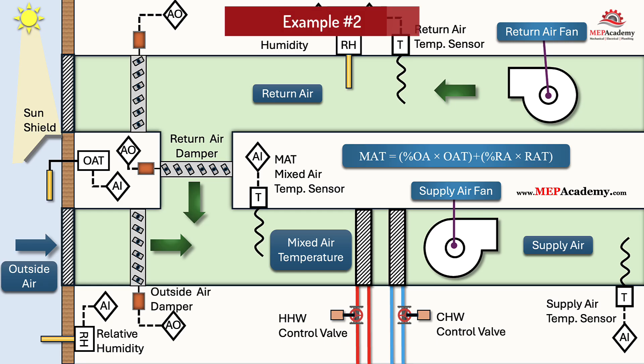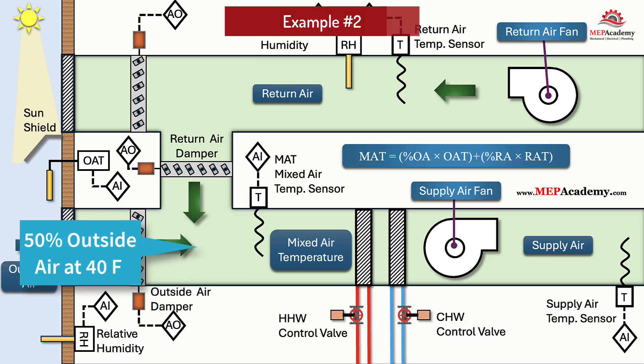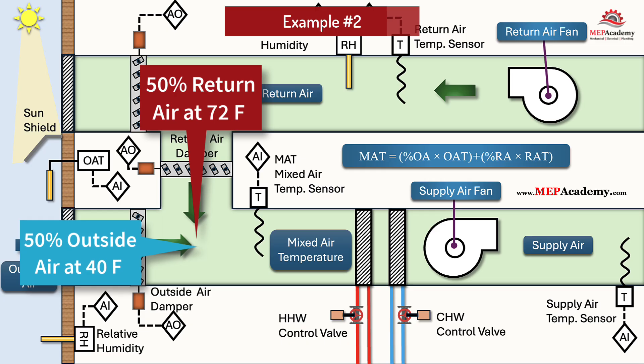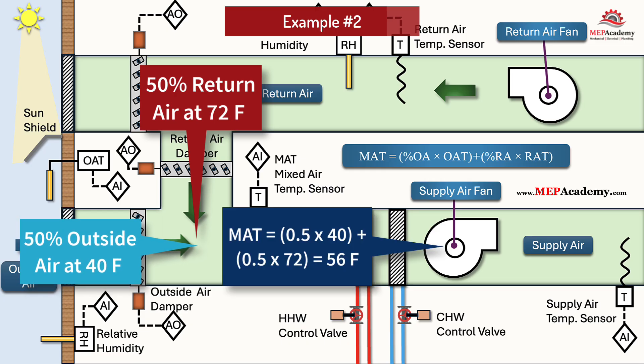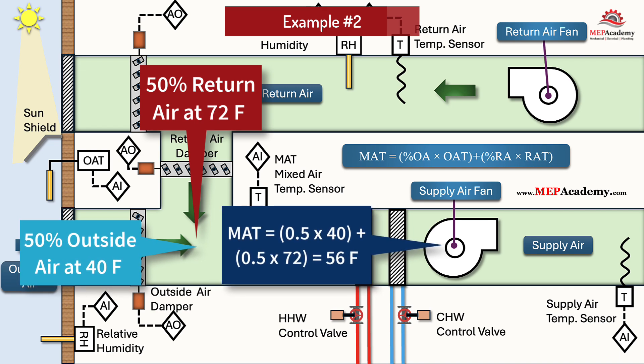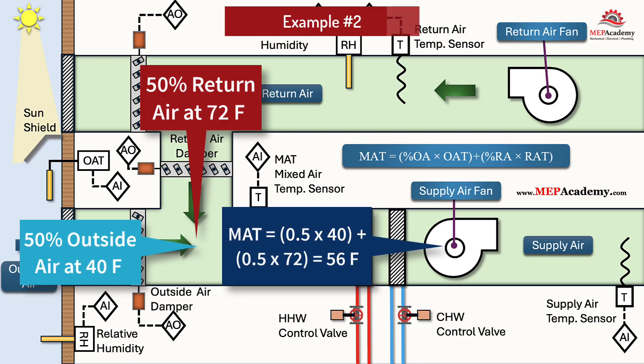Example 2 — 50% outside air: Outside air = 40°F, return air = 72°F, outside air = 50%, return air = 50% of total air volume. Mixed air temperature = (0.5 × 40) + (0.5 × 72) = 20 + 36 = 56°F. The coil sees 56°F mixed air temperature.